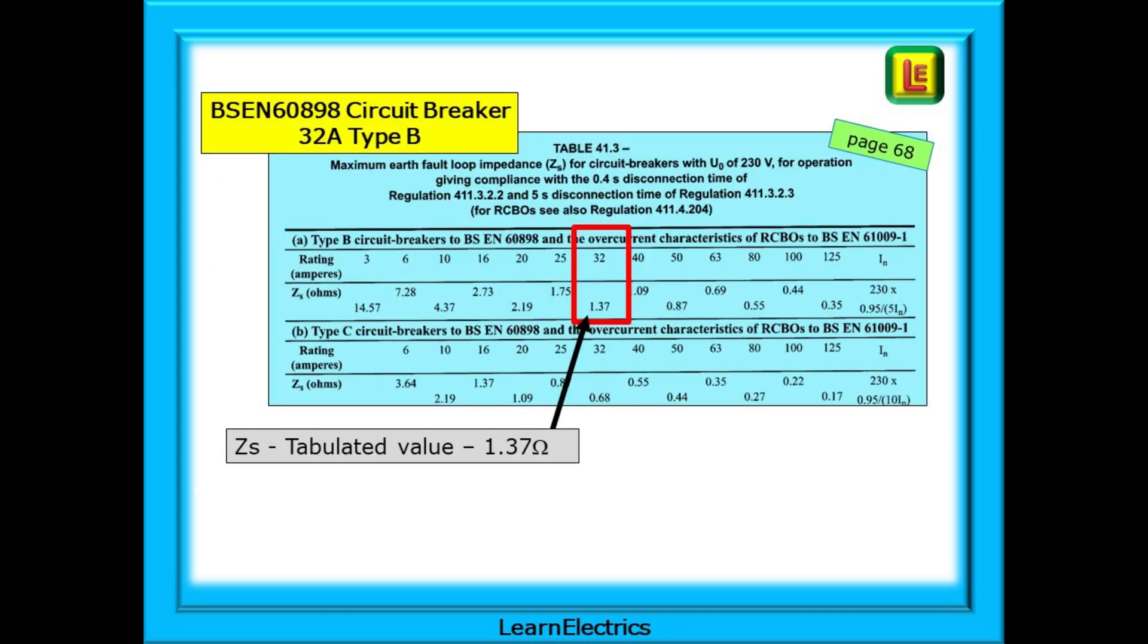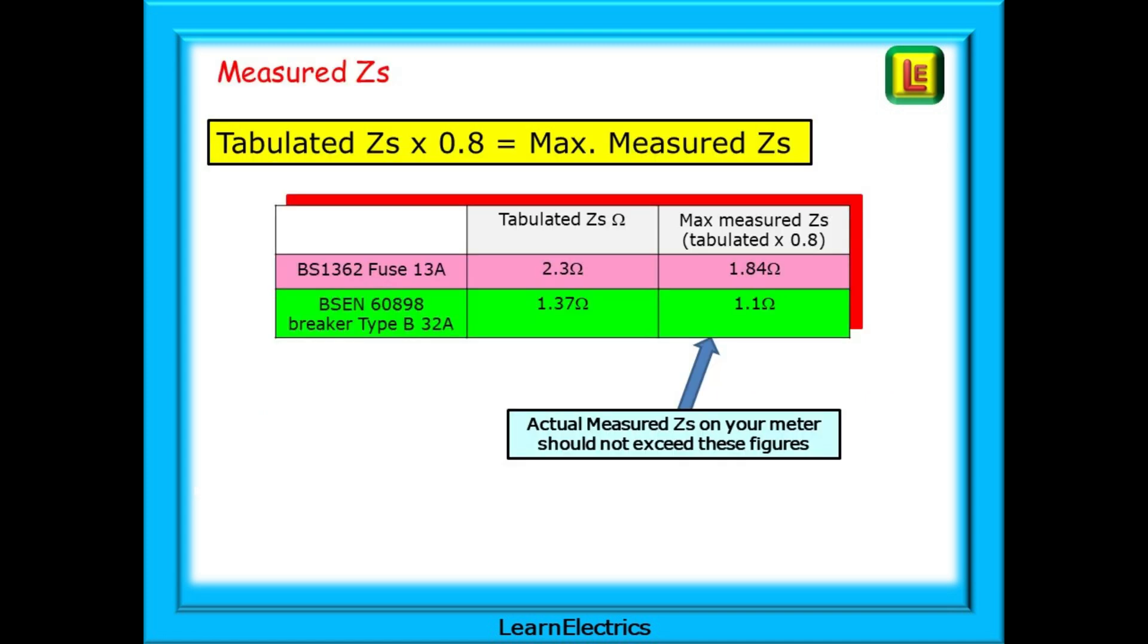And for the BS EN 60898 circuit breaker, table 41.3 on page 68 will give us the tabulated value for a 32 amp type B device. This is 1.37 ohms and again it needs adjusting for the maximum measured on-site values. Tabulated values, those taken from the tables in the regs book, should be multiplied by 0.8 to arrive at the 80 percent maximum permitted measured ZS value.